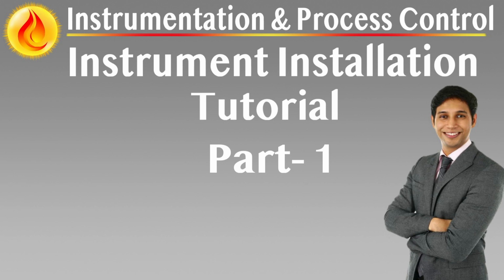Mounting remote instruments, structural integrity, and accessibility in harsh conditions. Instrument mounting supports engineered stability with environmental compatibility. Remote mounted instruments require robust, dedicated supports to ensure structural stability, vibration resistance, and ease of access. These supports must be independent of piping loads and must maintain proper alignment and rigidity throughout all operating and environmental conditions.